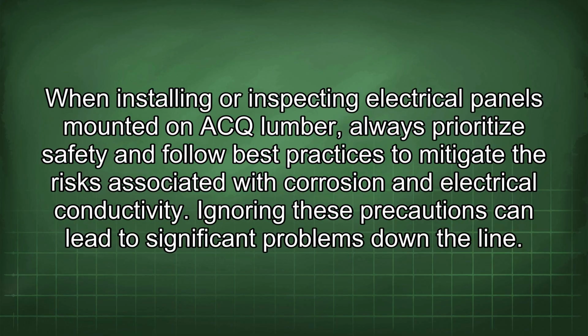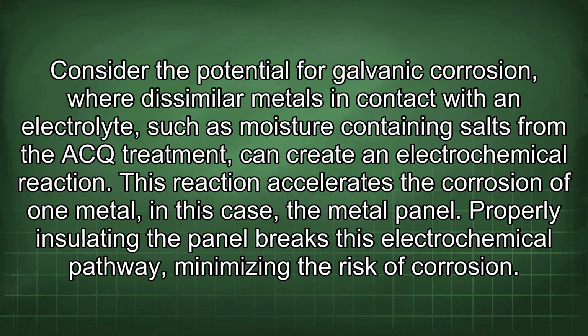When installing or inspecting electrical panels mounted on ACQ lumber, always prioritize safety and follow best practices to mitigate the risks associated with corrosion and electrical conductivity. Ignoring these precautions can lead to significant problems down the line. Consider the potential for galvanic corrosion, where dissimilar metals in contact with an electrolyte, such as moisture-containing salts from the ACQ treatment, can create an electrochemical reaction. This reaction accelerates the corrosion of one metal, in this case, the metal panel. Properly insulating the panel breaks this electrochemical pathway, minimizing the risk of corrosion.